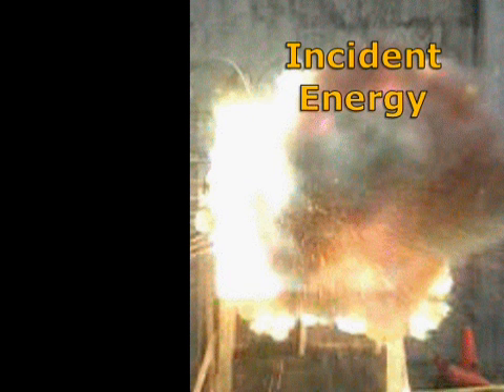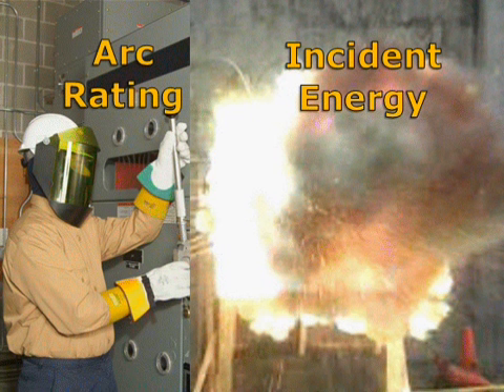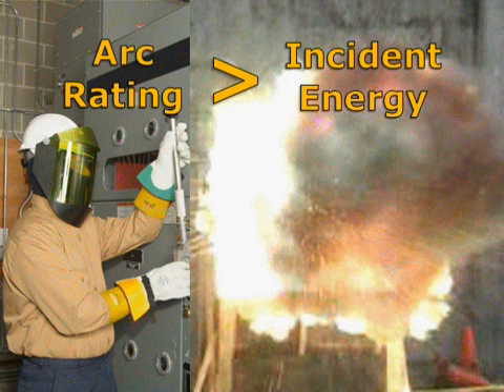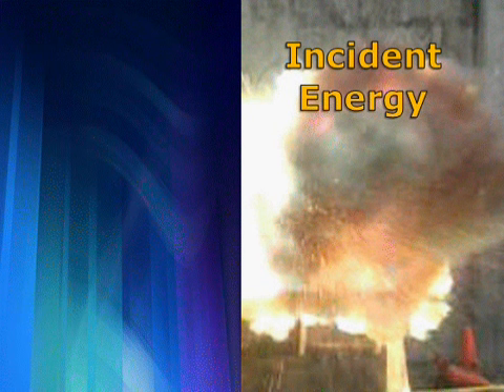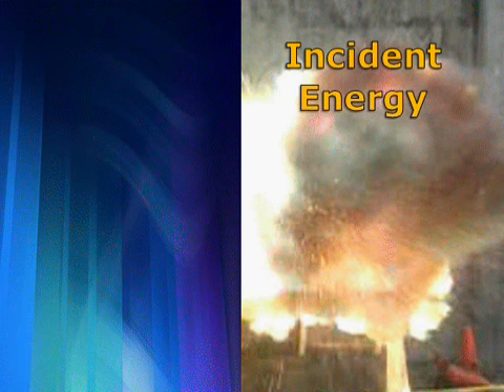And the real scope of an arc flash study, the fundamentals of it, is number one, you want to calculate the incident energy, and that's what a lot of the software will do. If there's an arc flash, how much energy may be available? And then you compare this to the arc rating of your protective equipment. And so that's the general scope. Now, the incident energy, there's a lot that goes into the incident energy.